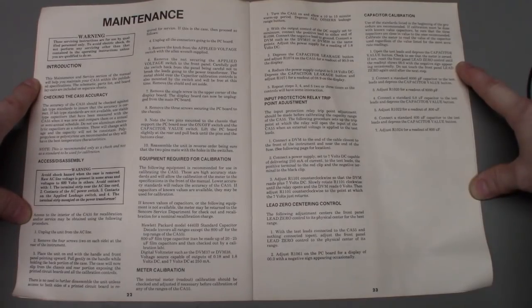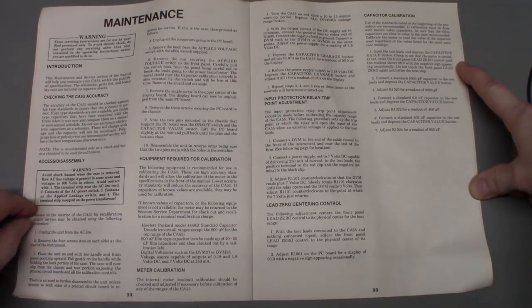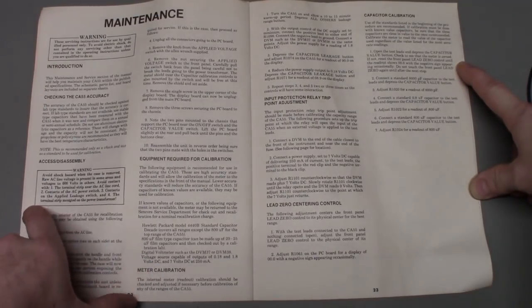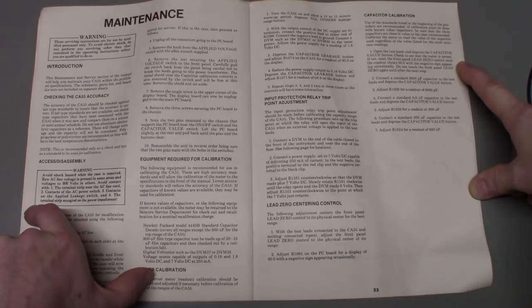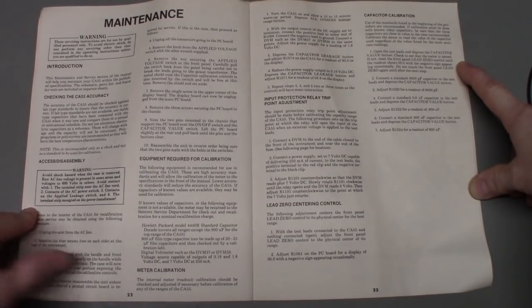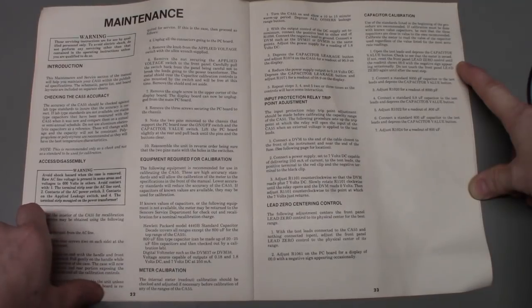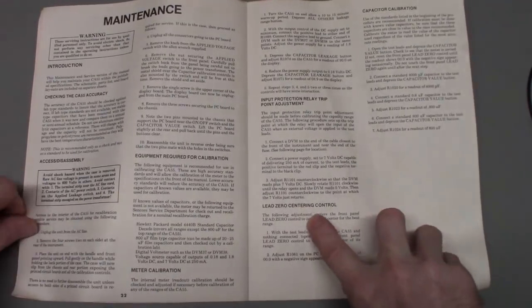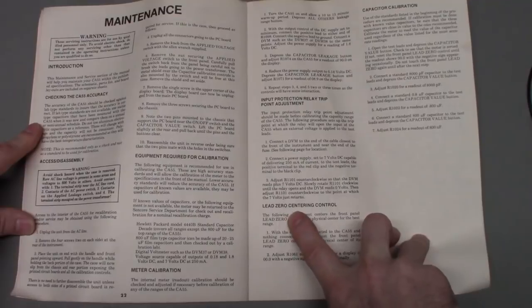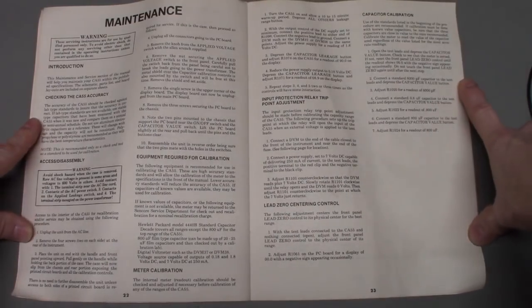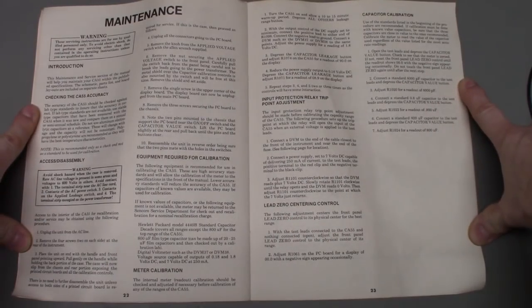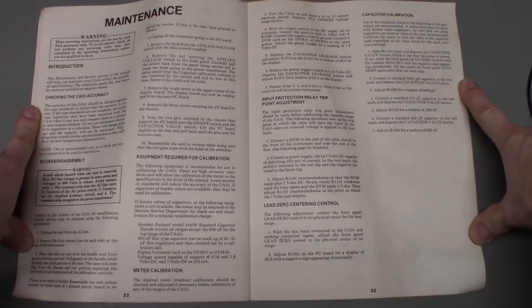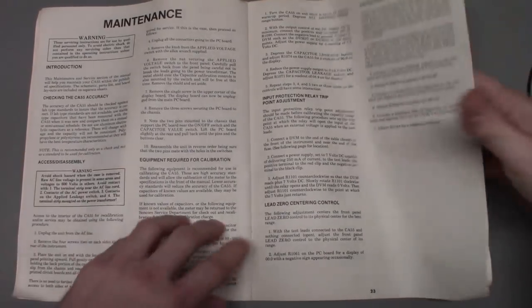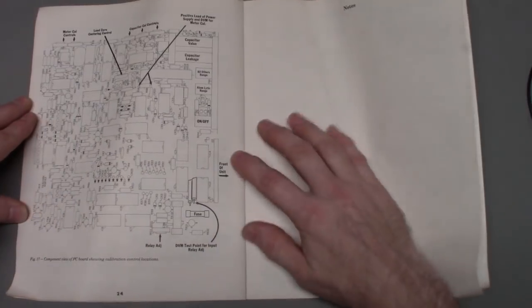This is the calibration procedure right here. So this is the page you're going to want to zoom into and read. The only thing in this one that really needs to be calibrated is this right here. The probe compensation 0. I think that's internal meter reader or whatever it was. No, right here. There it is. I'm looking through the viewfinder. The lead 0 centering. It's not perfectly centered, so I do need to calibrate that. But as far as capacitors, I tried all the capacitors, and yeah, worked just fine.